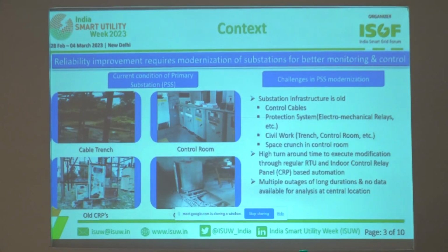Now, what are the challenges for this PSS modernization? As you may already know, for a 33 by 11 kV substation there are a lot of control cables. The infrastructure consists of control cables, protection systems. In today's world of numerical relays, there are substations which are still served by electromechanical relays. Civil work, trenches, control rooms - a huge cost is involved in refurbishment and modernization of these, and of course there's high turnaround time and cost. So if you have to take a shutdown of a primary substation, you can imagine the kind of agitation the customers would face because of the high outage time.